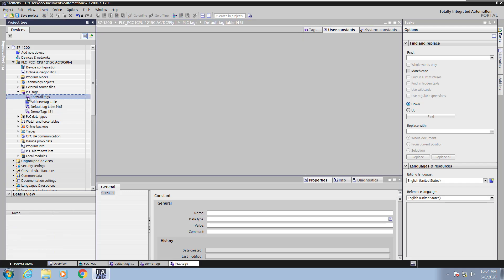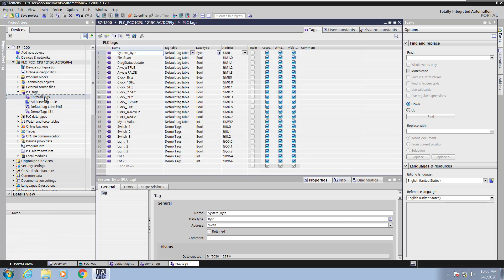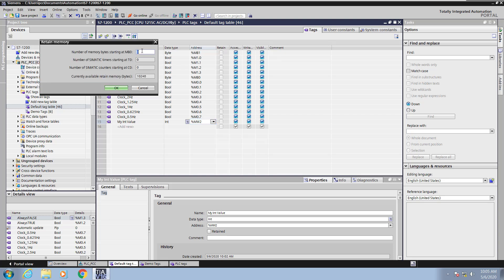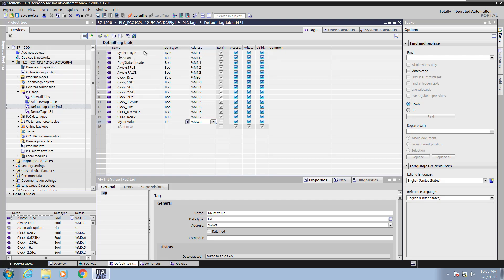Next I'm going to open up the show all tags view. This allows you to see all tags from all tag tables in one view. You can also configure the retentive settings in the show all tags view. I'm going to open up the default tag table so you can see just the tags in the default tag table. Now I'm going to open up the retentive settings and configure two bytes to be retentive. Any tag that falls within the first two bytes will be flagged as retentive, so there will be a check mark next to the tag.